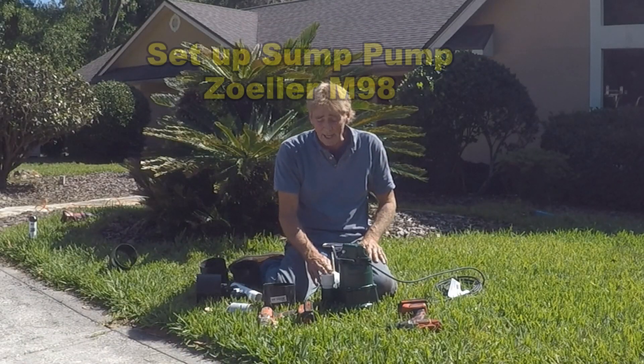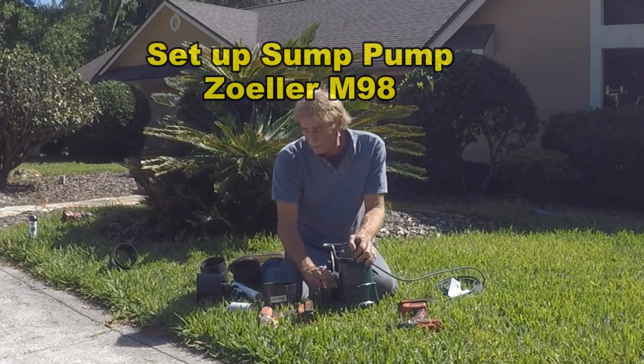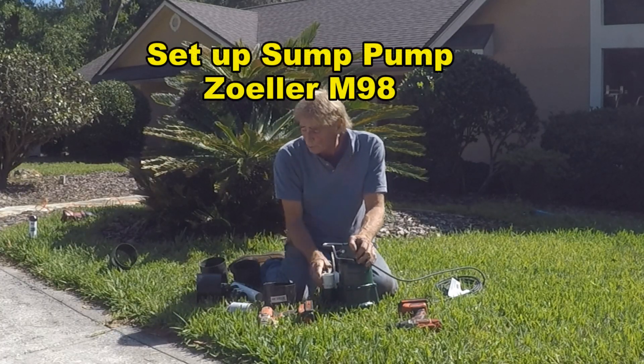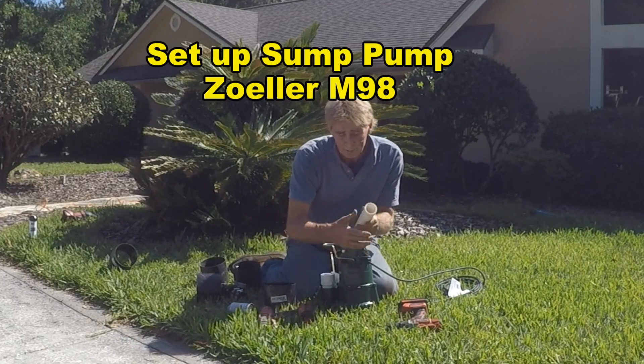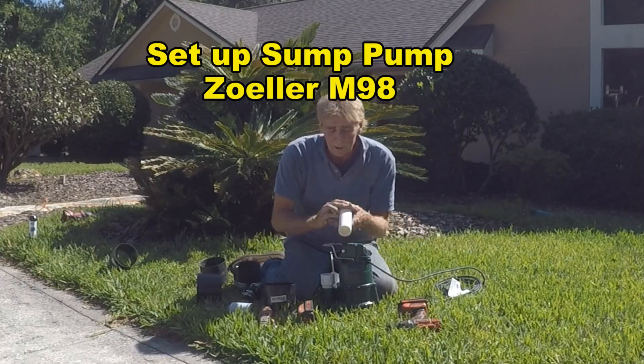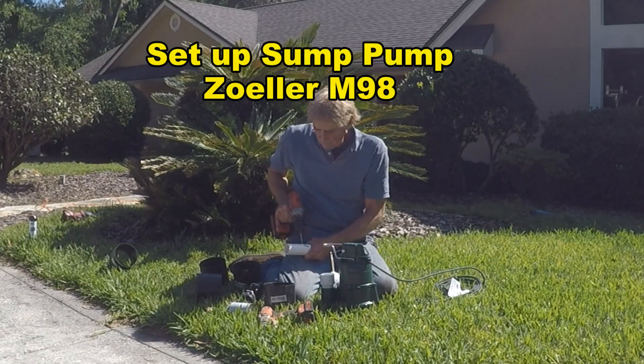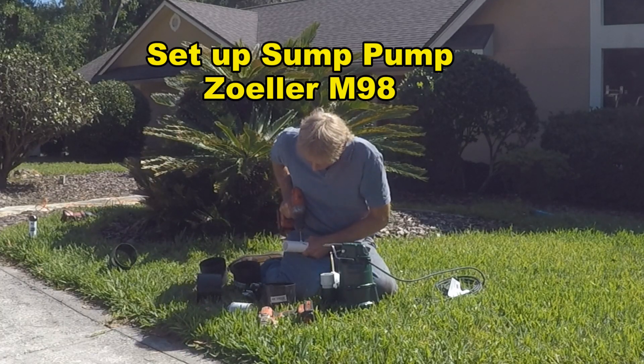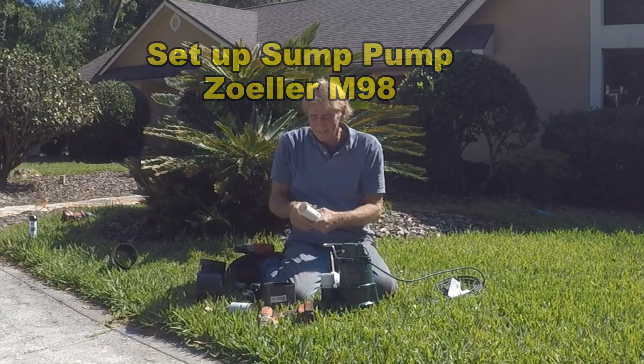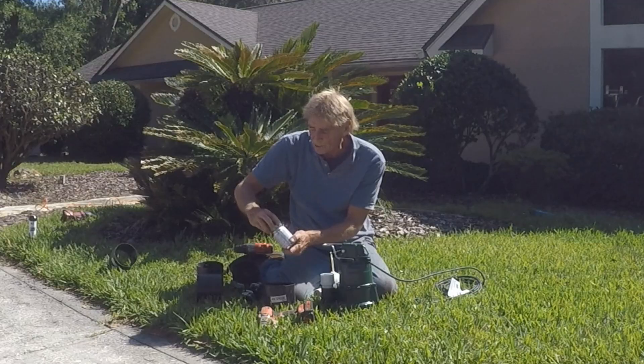Let's set up the Zoeller M98. It starts with a male threaded inch-and-a-half adapter — we've already screwed that in. There's a port and a slot; you just screw it right in. Next we're going to put a small riser on here just to get above the bar, then put the check valve on. We do need to drill a 3/16-inch hole into the pipe as a pressure relief.